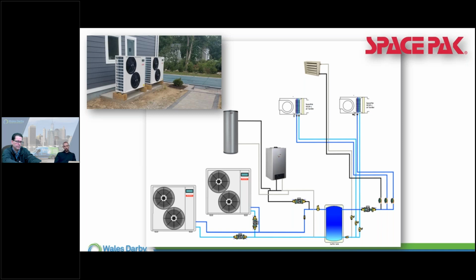If you have some applications you're thinking of, definitely reach out to us. But you throw an electric water heater in the mix and get a small braze plate heat exchanger off that buffer tank, we can go with a flow switch there and really feed that tank, let's call it 110, 120 degrees of water, we can get a little higher. I say 120 because that's the sweet spot, but the machines can get up to 130. So if I can put 120 degrees into a summertime electric water heater application, that's perfect. Even if I put just 110 into the tank, how hard does that electric water heater have to work?